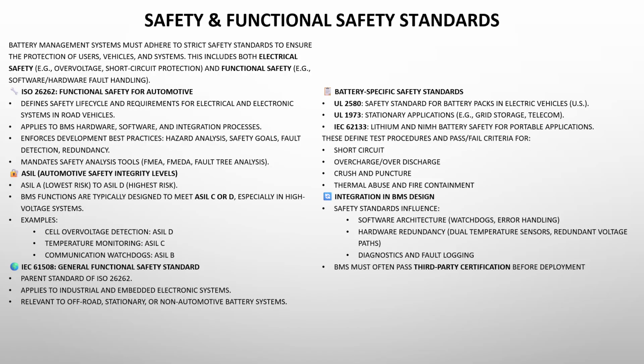Extremely structured. Under ISO 26262, different safety functions get assigned an ASIL, automotive safety integrity level. It goes from ASIL A, lowest risk, up to ASIL D, highest risk. Critical BMS functions, like detecting an overvoltage condition that could lead to fire, that's typically ASIL D. Temperature monitoring might be ASIL C. The level dictates how rigorous the design, testing, and validation have to be.